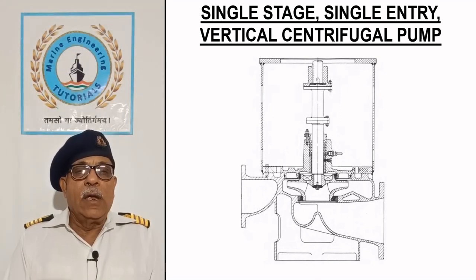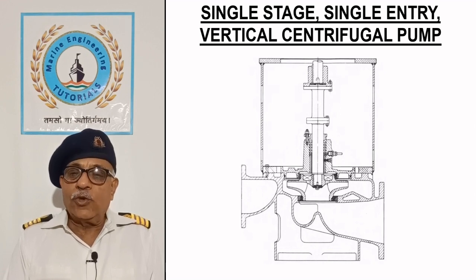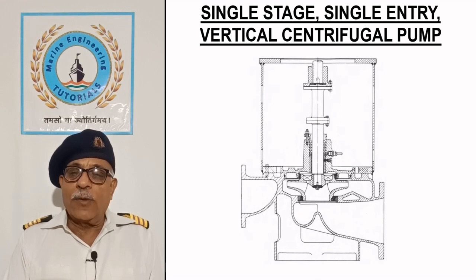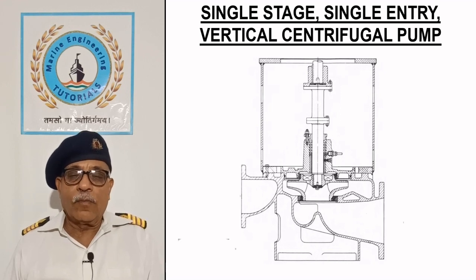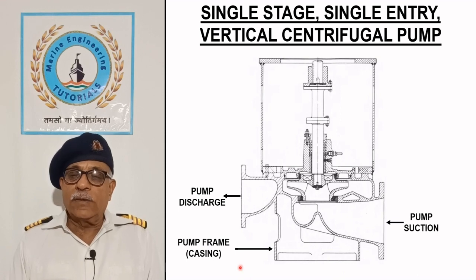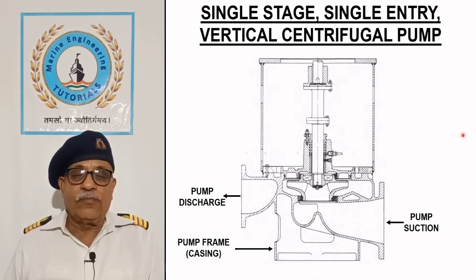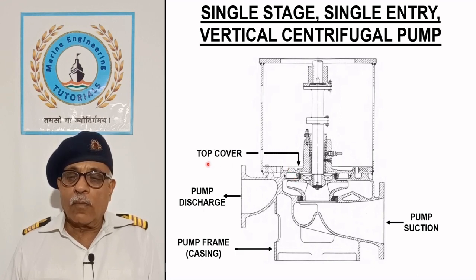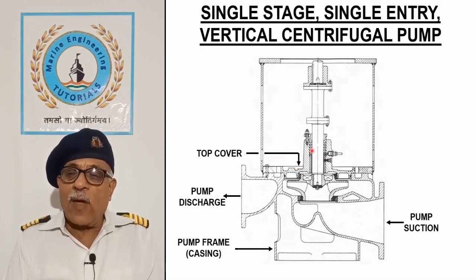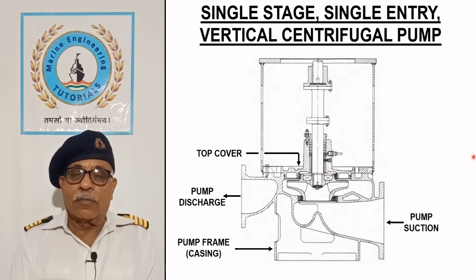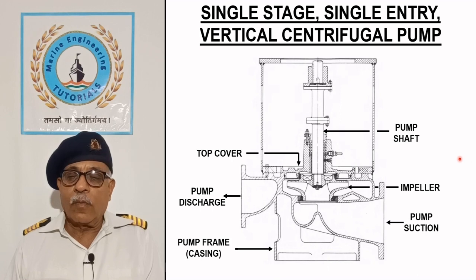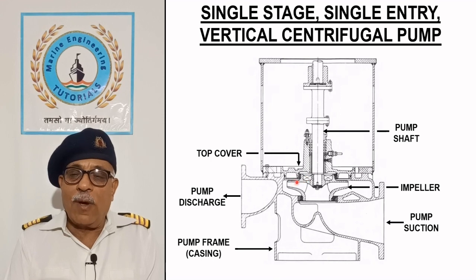Single stage single entry vertical centrifugal pump: the sketch shows the construction and operation of a single stage single entry vertical centrifugal pump, which is a common element on ships as it saves space. The pump consists of a casing mounted on its foundation and is equipped with suction and delivery connections. The top cover consists of a line bearing for supporting the shaft, where the liquid being handled provides cooling and lubrication. The pump shaft passes through the top cover and is attached to the impeller with the help of a key and a nut.